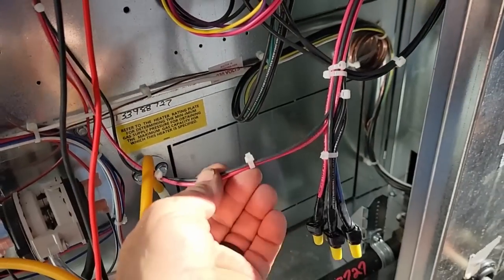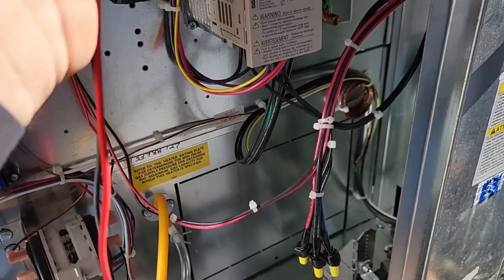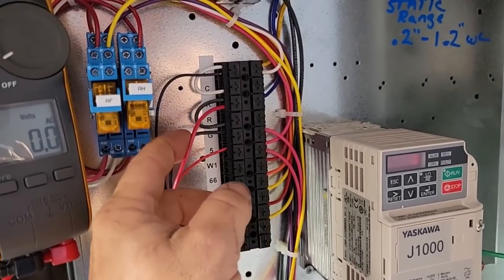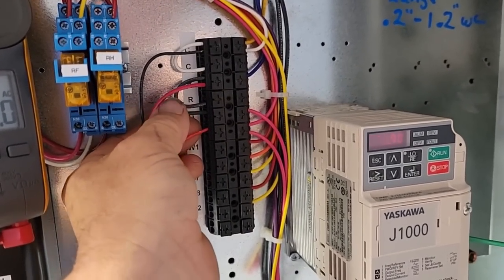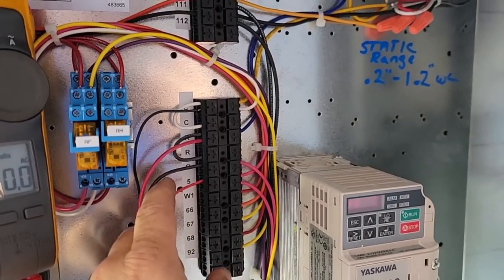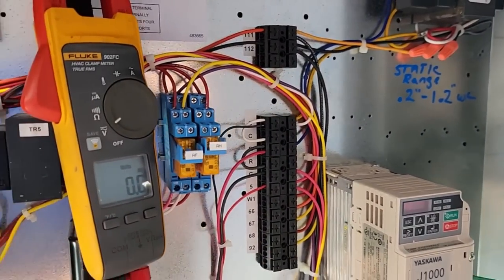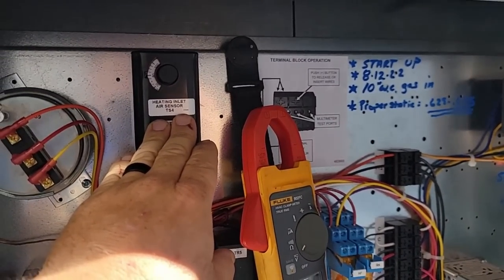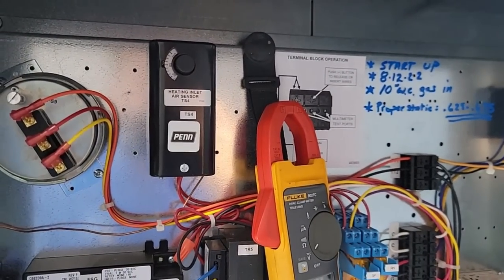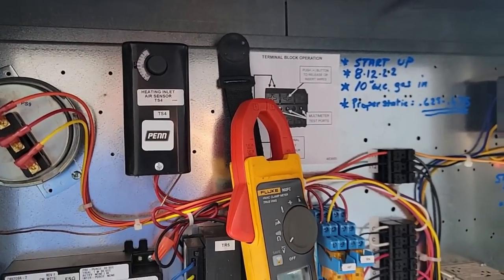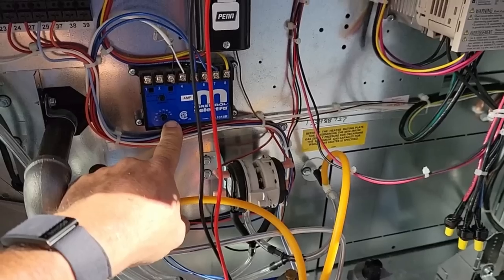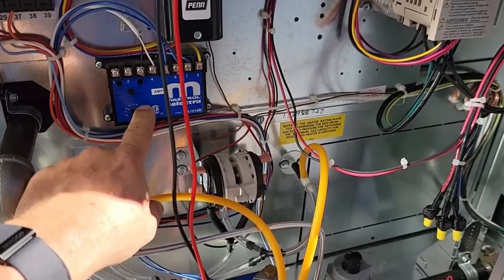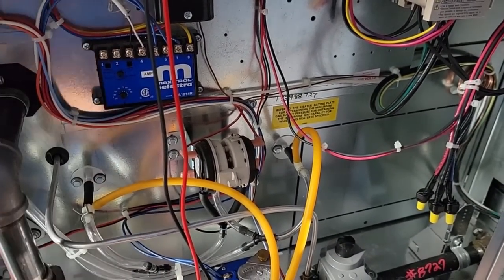What we've got right here is two wires coming from R and G, which is coming in right here and G here. We're gonna have to jump G to W to get heat, then when it's cold enough, it'll automatically switch over and bring on the burners. Then this control here, so if it's 0 degrees outside, it's gonna put out 70 degrees. That's the design of it.